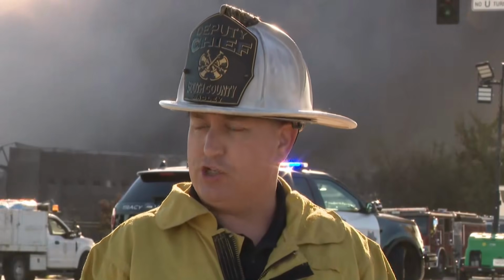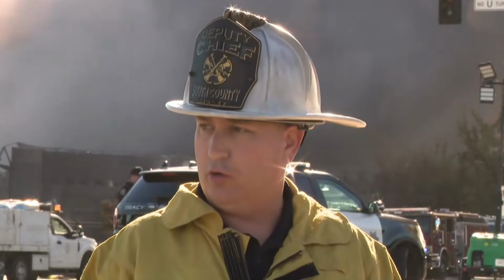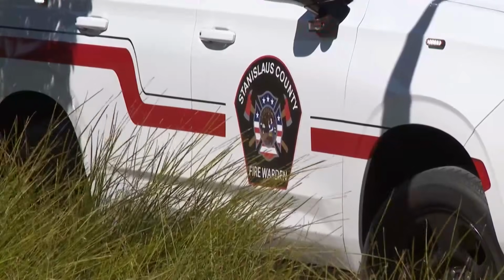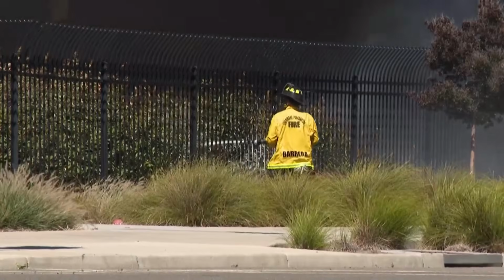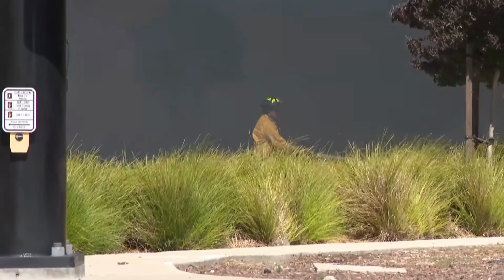Brian Bagley, South San Joaquin County Fire Authority Deputy Chief, says in this case, the sprinkler system was tested by a sprinkler company, an alarm company, in January of this year, and it was completely signed off. However, when our crews were engaging in the firefight, they did not recognize any fire sprinkler activations at all. He says the fire marshal on scene inspected the fire pump room and saw there was zero water pressure. So we knew that there was no water flowing, which all of that fire pump also supplies the yard hydrants directly adjacent within the facility itself. And so we had limited to no water coming out of those hydrants.